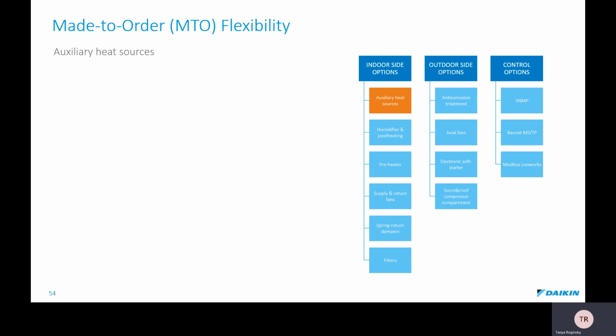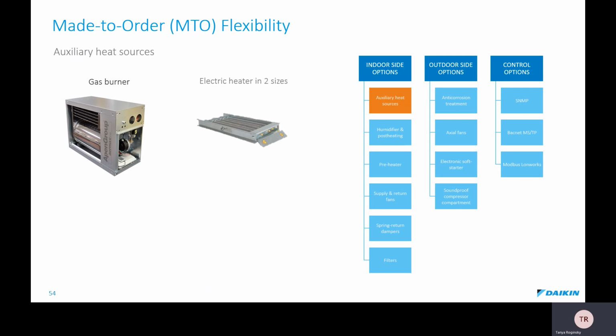First of all, auxiliary heaters to choose from. You can have gas burner, electric heater, or hot water coils. For the gas burner, the capacity is on average 103% of the total unit capacity, and it can work with both methane and propane. For the electric heater, there are two different sizes. One which provides 26% of the total capacity, and second one which provides 39% of the total capacity on average.